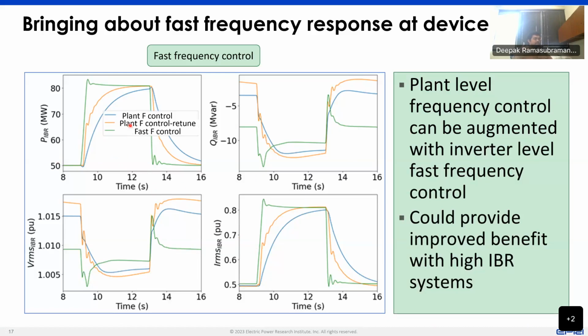And that will give you a little bit of improvement in performance, but soon it may become unstable if you try to make it too fast, because there are communication delays involved between the plant controller and the inverter controller. And if you go down to inverter level control, or fast frequency control at the inverter level, you start getting a much better response. You start getting a much better benefit.